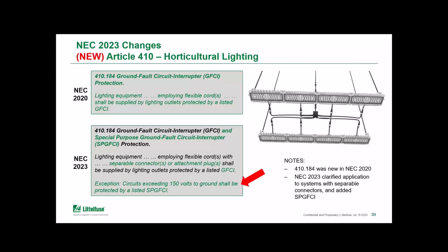The code did mention all systems employing a flexible cord, but that was actually a wider requirement than the code panel had really intended. So in 2023, they corrected that language to say that lighting systems with flexible cords and separable connectors and plugs is where the GFCI requirement comes into play. That was the intended target all along. Since 2023 NEC was also adding special purpose GFCIs, the code making panel also took the opportunity to add that requirement to have lighting circuits above 150 volts to ground use the special purpose GFCIs as well.